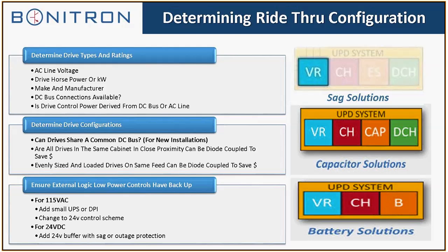Determine drive types and ratings, AC line voltage, drive horsepower, kilowatts. We don't care. You can even give us amps, and we can take the parameter and figure out what it is from there. Make and manufacturer of the drive, kind of important, but not critical. It's just good to know if there's anything that's going to bump heads with the ride-through. DC bus connections available, that is critical. And control power for the drive. Once again, if you don't back up the control power, backing up the drive does you no good. We can also work with common bus drives.